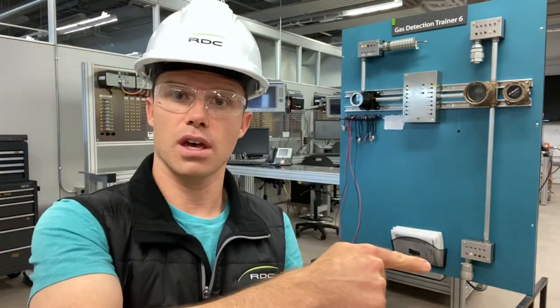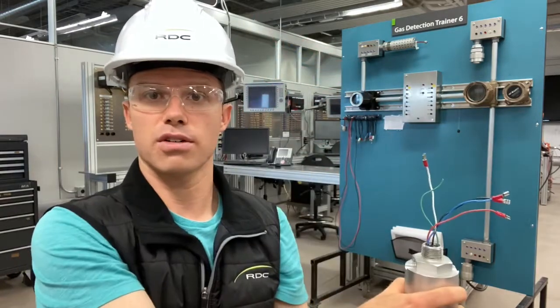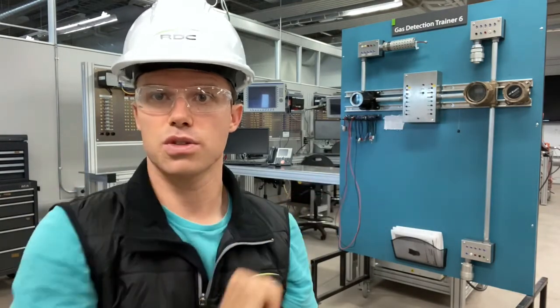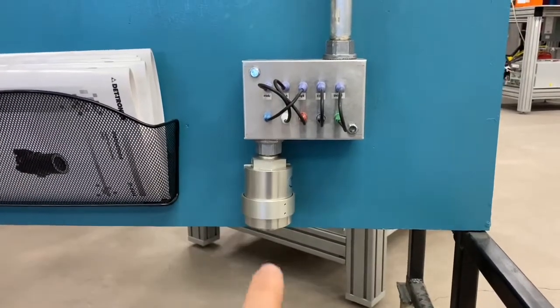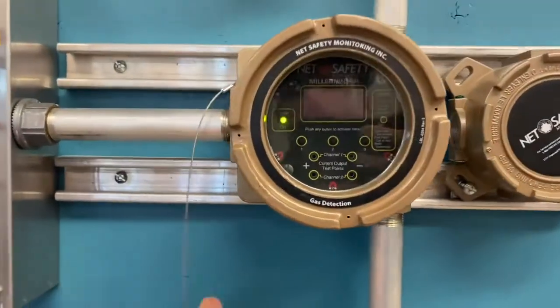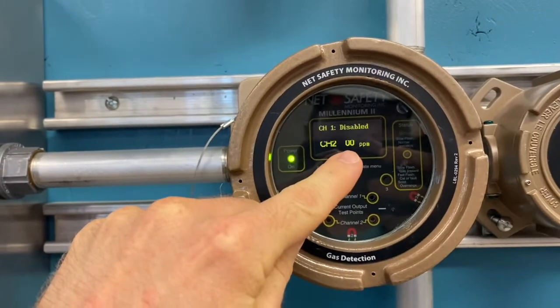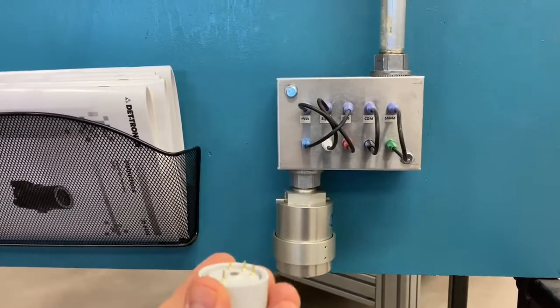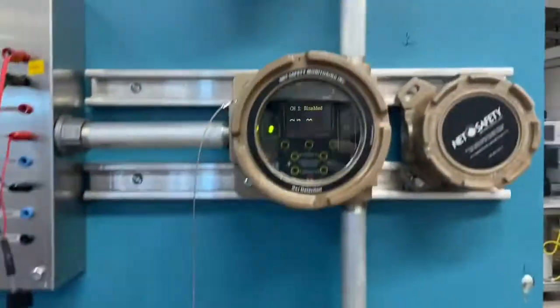Just to bring you guys in closer, down to our electrochemical cell — here's the housing that I pulled it out of. It's mounted right down there, and we're going to wire it all up. Up top here, this shows it will display the concentration that we're measuring. Our electrochemical sensor is mounted down low for H2S. If we follow this conduit right here — if I just wave this magnet — there you can see it's giving us a concentration in the ambient air of H2S. You can see it's at zero PPM, so low concentration, meaning there's very little current flowing through the electrodes.